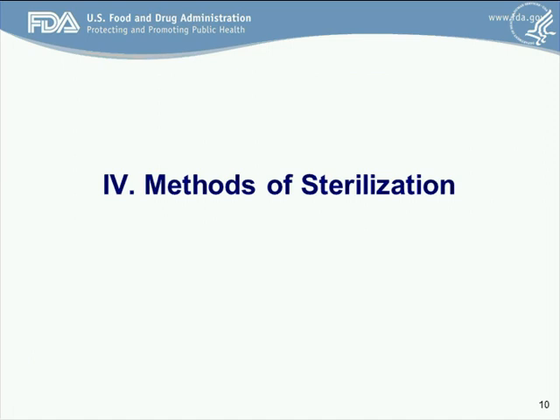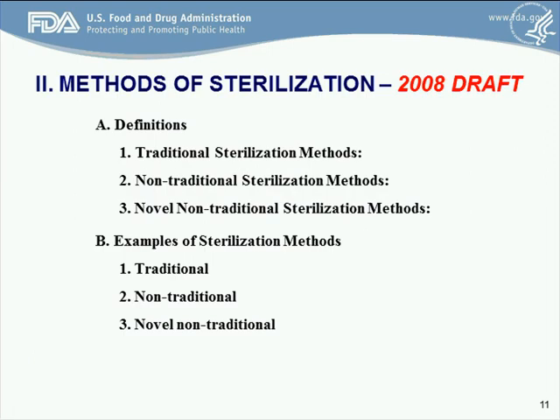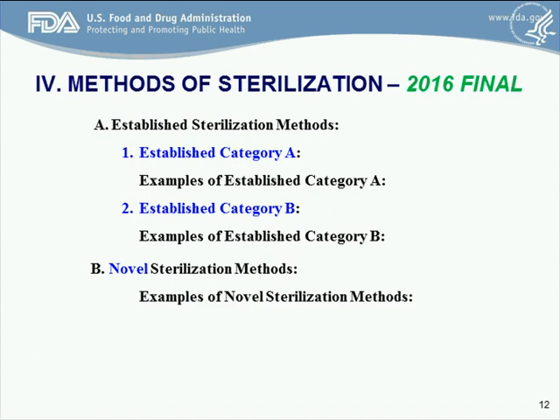Moving on to methods of sterilization, you may recognize these methods from earlier versions of the guidance document: traditional sterilization methods, nontraditional sterilization methods, and novel nontraditional sterilization methods. In the 2016 final version, the nomenclature has changed. Now we're looking at established category A, established category B, and novel sterilization methods, with examples of each sterilization method integrated into each section.